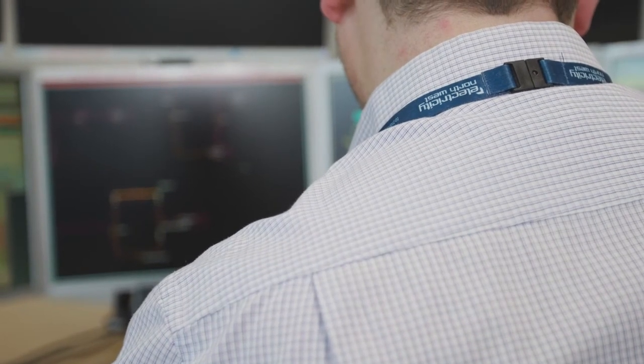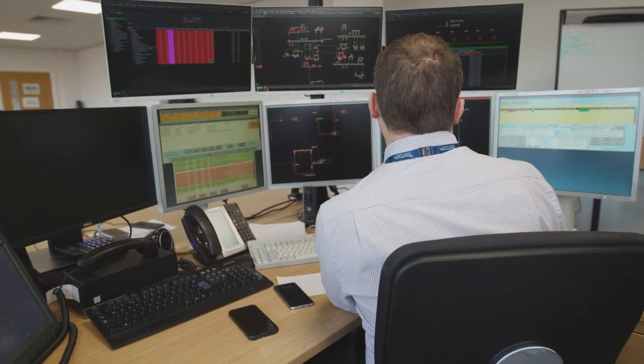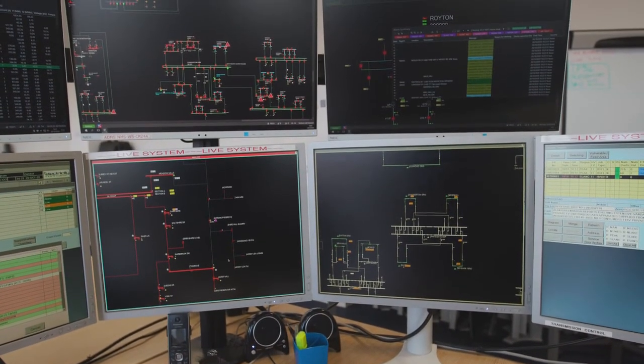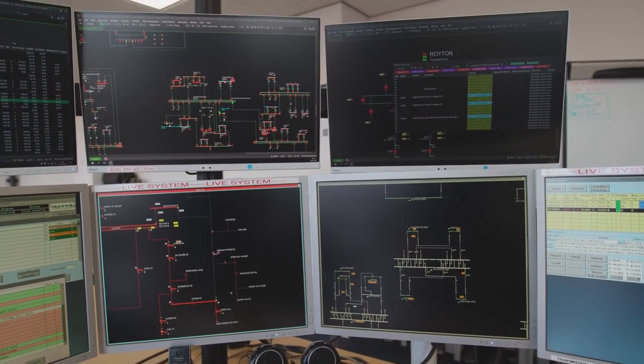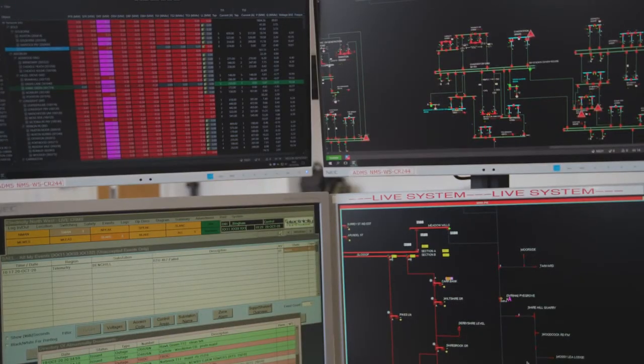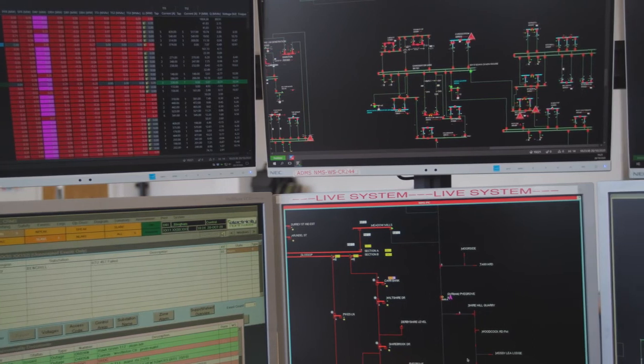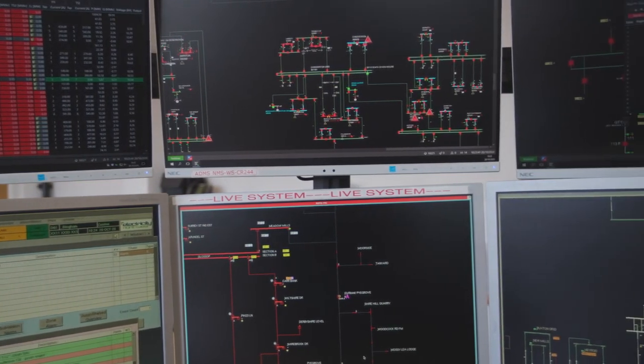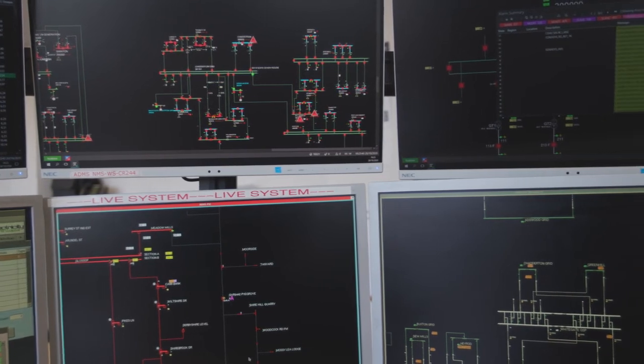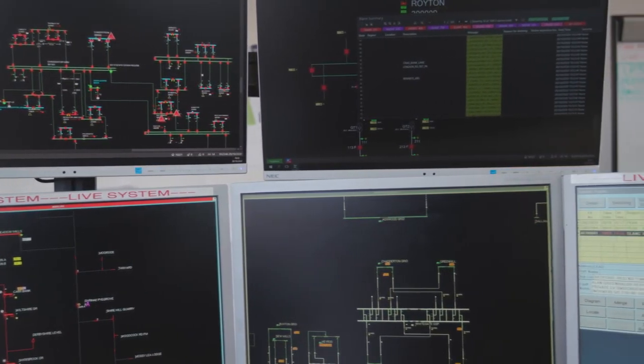It wasn't part of the project at this moment in time to have real-time reporting. It's basically proving the concept at this stage. However, there is another phase of the project which is implementation of Sentinel into the network management system, which will be close to real time. This is all based on the development of the algorithms and the triggers to operate in a very short period of time. So what we're doing in the interim is applying a soft approach whereby Kelvatech will develop the algorithms, and it'll be a reporting system.